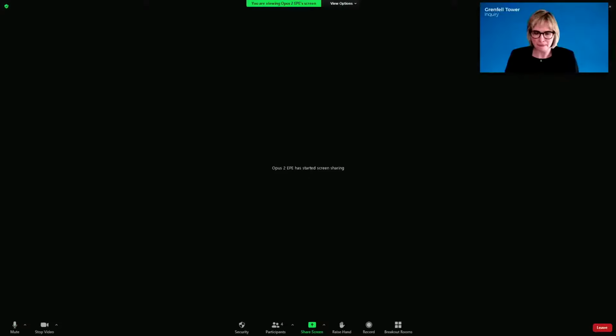Yeah, the only guide... I'm going to ask the question again. Why do we not see any consideration in the design documentation about maintaining tenable conditions in the lobby? Because it isn't the practice of the industry to achieve tenable conditions in corridors unless they're really extended, between 15 and 30 metres. Mr. Hanson, I'm sorry, Ms. Granger, I'm just going to come in. You said a moment ago that you didn't think this applied to the case we're considering. Did I understand? In the context of the question, because the question that's been put to me is the suggestion that these corridors should have had tenable conditions, and that should have been part of the design. So we've only looked at tenable conditions in long extended corridors between 15 and 30 metres, and there is a direct requirement for those corridors to have tenable conditions.